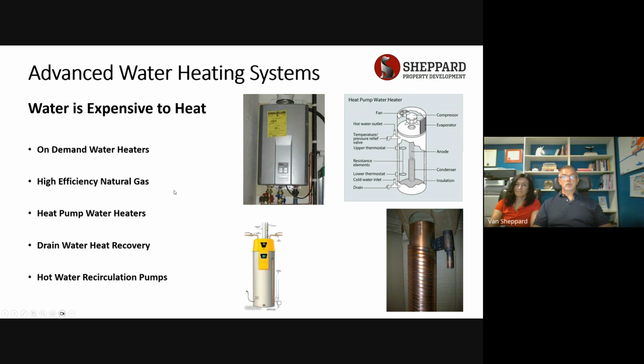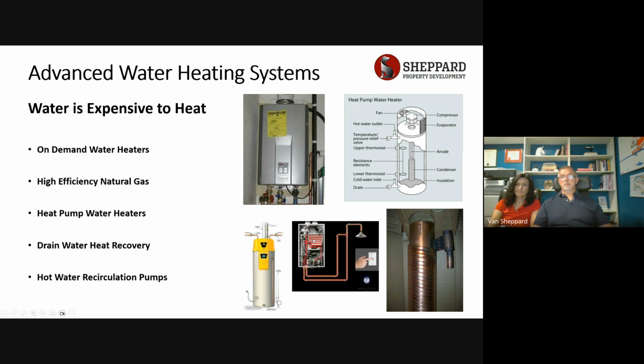And then we have hot water recirculation pumps, and it's a way that you can use an on-demand hot water heater. One of the complaints about them is that you can turn on the hot water in your bathroom and you can wait sometimes up to a minute to get hot water at the source. So the newer ones now come with a built-in recirculation pump and a small reservoir inside the heater. And you can set up a return loop that keeps hot water in the system so that when you turn it on, you get hot water instantly or virtually instantly, very, very quickly. There's no wait for the thing to start up. You've already got that little reservoir of water to supply. And that's an improvement in quality for your occupants, that you get hot water right away. And it means you waste less water as well.